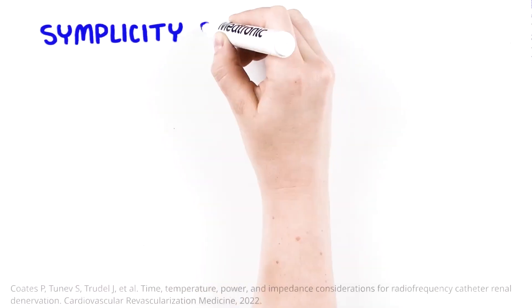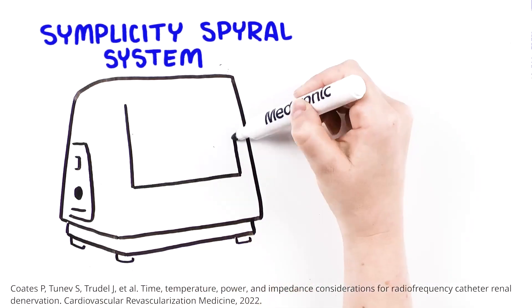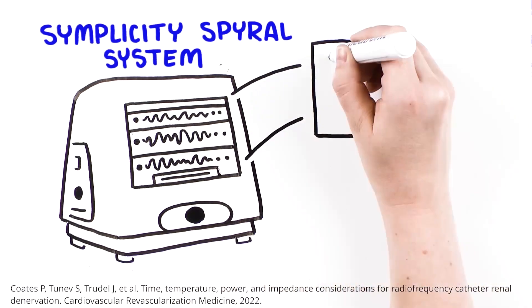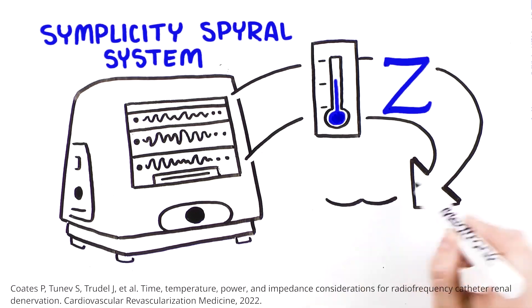In addition, the Symplicity Spyral system contains a unique real-time and responsive algorithm. This algorithm precisely modulates each electrode based on temperature and impedance signals to achieve safety and effectiveness.